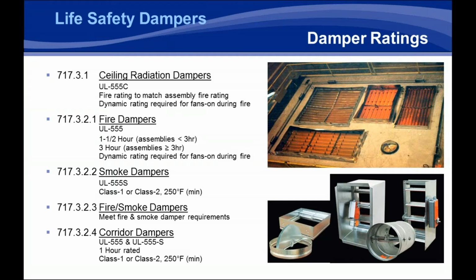And we, as a ceiling radiation damper manufacturer, urge engineers to put in any type of smoke detection and that shutdown that's required for air handlers above 2000 CFM on all their air handlers to make sure it is a static system, as if you're penetrating a rated ceiling, you only have static ceiling radiation dampers available for those penetrations. It's new to the code, and we're glad that the code realizes the requirement is there, but unfortunately it will be much more likely that the need for smoke detection to shut down the air handler will be used for quite some time, as many ceiling radiation damper manufacturers throughout the industry don't feel they can actually pass the testing required for these dynamic rated ceiling dampers.